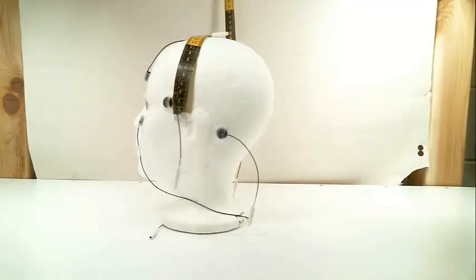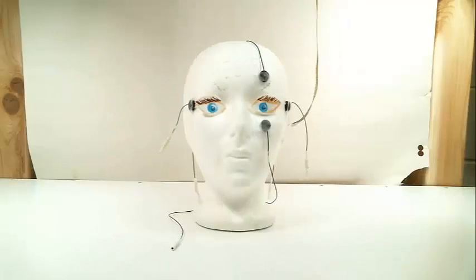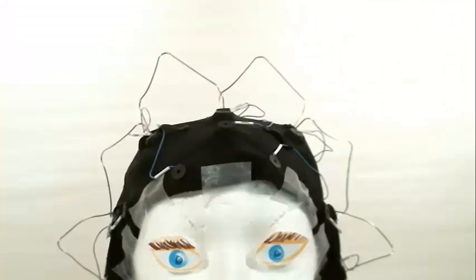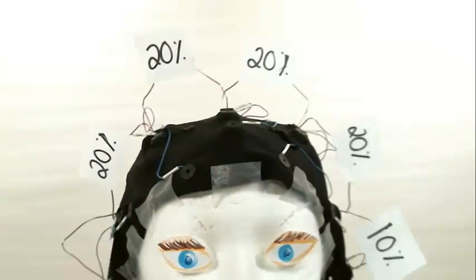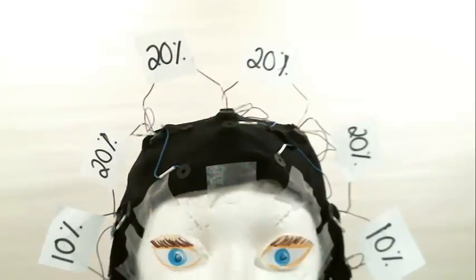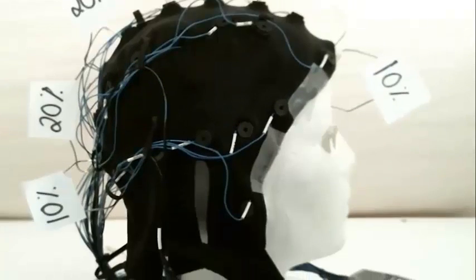Then we measure across the head from preauricular notch to preauricular notch — that is, from ear to ear — and mark that with red as well. The placement of the cap is important because the electrodes are in a fixed position. The international 10-20 system refers to the distances between the electrodes: either 10% or 20% of the inion-to-nasion distance or the preauricular notch distances dictate where the electrodes lie on the scalp.